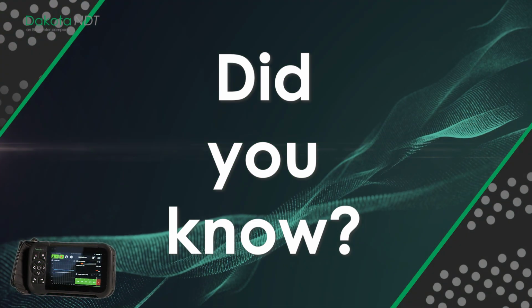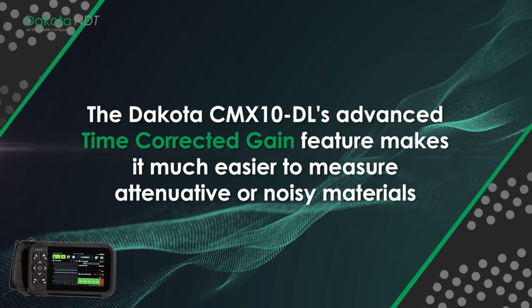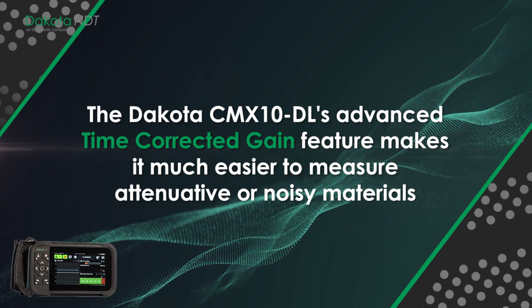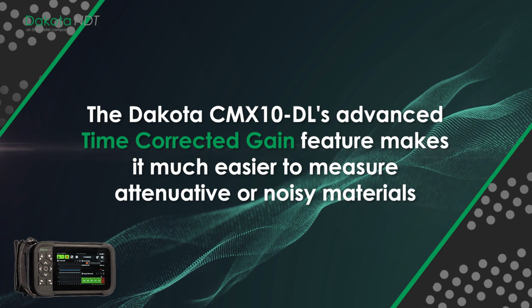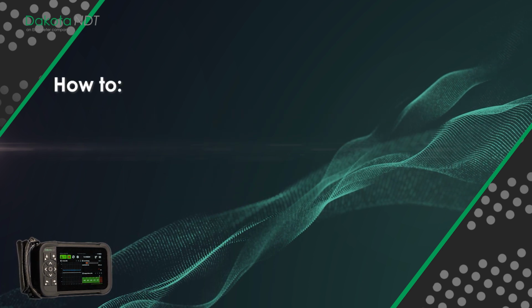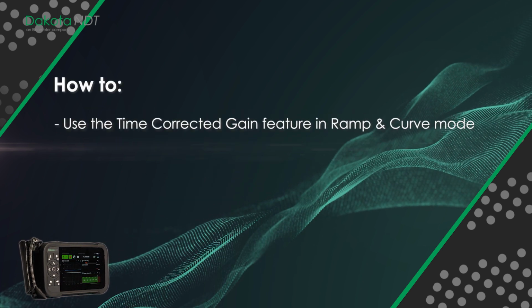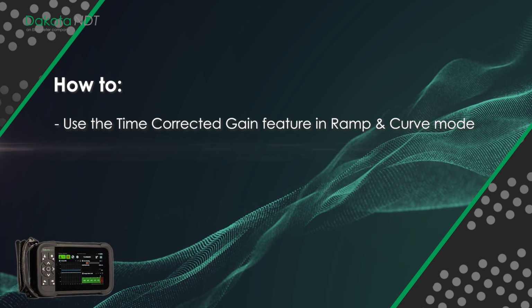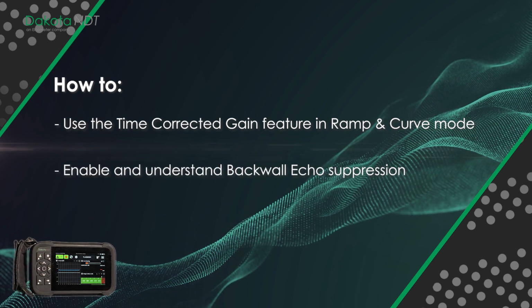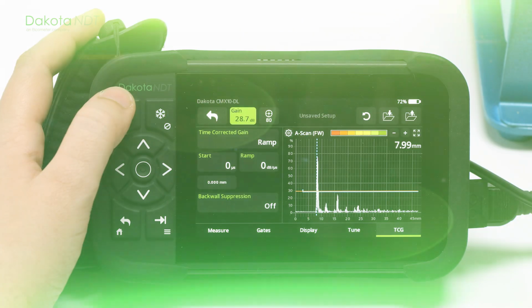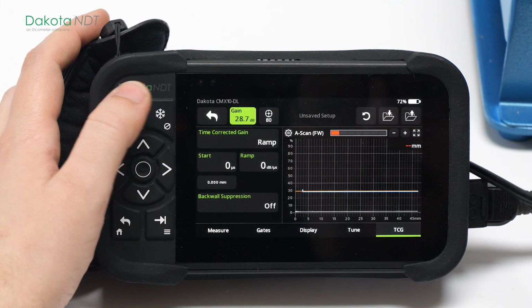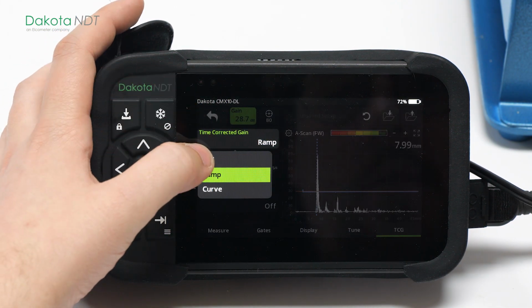Did you know the CMX10-DL's advanced time-corrected gain feature makes it much easier to measure attenuative or noisy materials? In this video, we will cover how to use the time-corrected gain feature in ramp and curve mode, enable and understand Backwall Echo suppression. The time-corrected gain feature can be found under the TCG tab on the main measurement page.